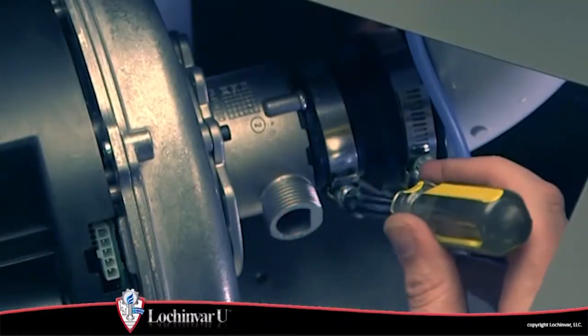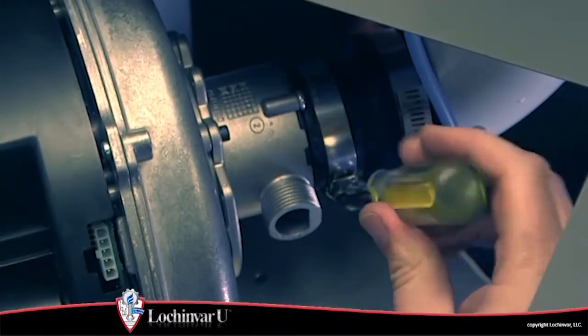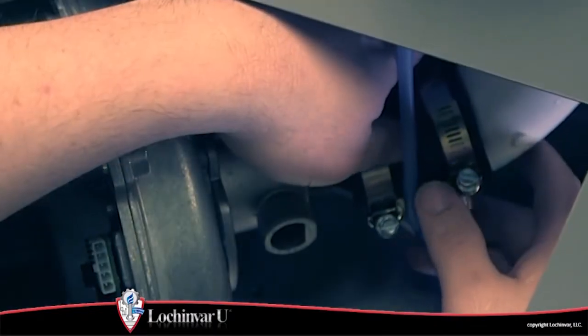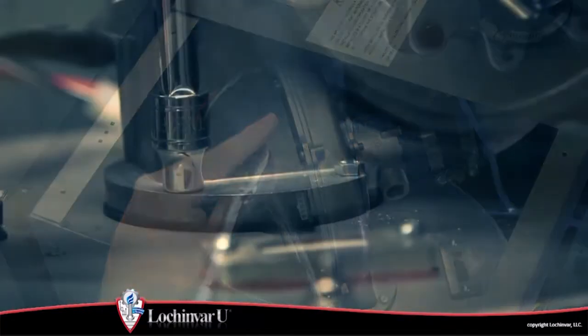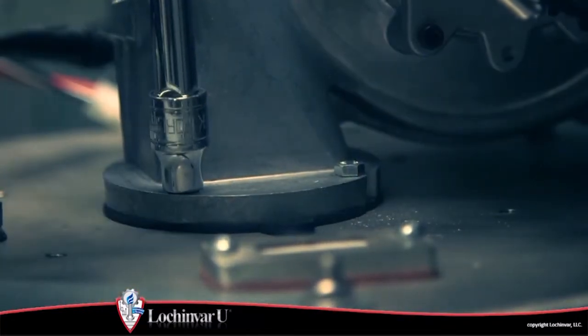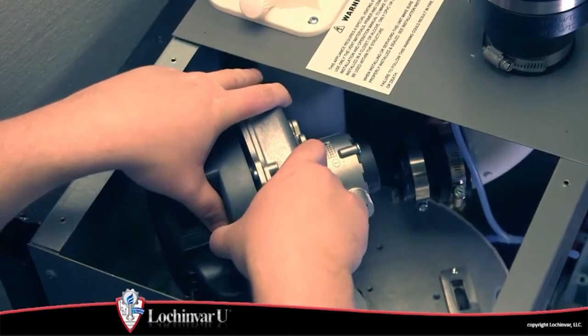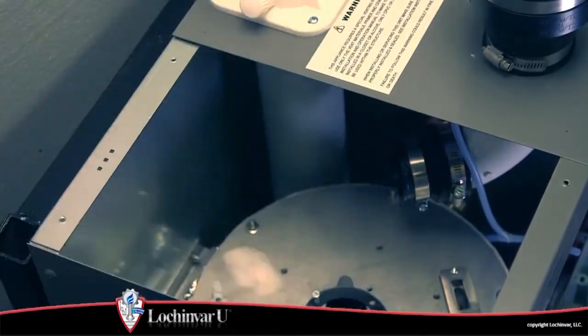Using a 5/16 inch nut driver, loosen the ratchet clamp that secures the air intake piping to the venturi assembly. Then, using a 5/16 wrench or socket, remove the 4 screws that secure the fan assembly to the heat exchanger top plate. Now remove the fan assembly and venturi from the unit.